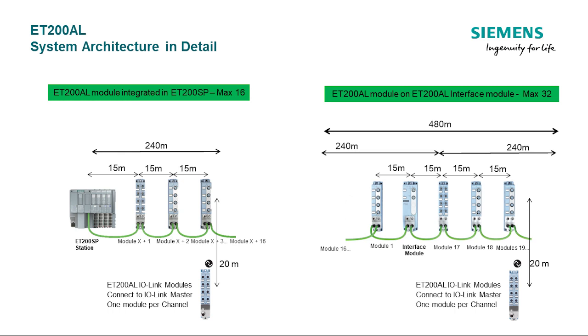There are no restrictions on I/O mix on either topology. You can freely use digital in/out, analog in and out, and I/O-Link modules. When using an I/O-Link master, modules can extend your system with a variety of different I/O modules which connect directly to the I/O-Link master port, located up to 20 meters from the module.